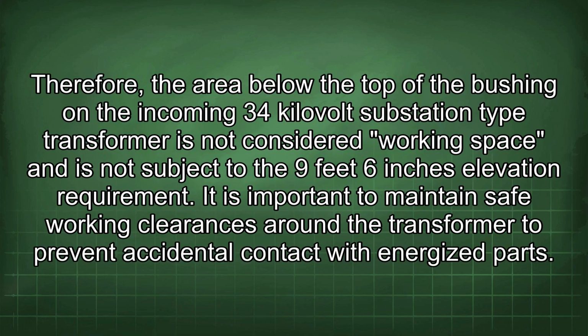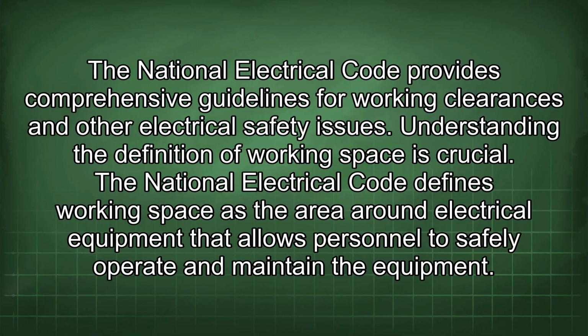Therefore, the area below the top of the bushing on the incoming 34 kV substation type transformer is not considered working space and is not subject to the 9 feet 6 inches elevation requirement. It is important to maintain safe working clearances around the transformer to prevent accidental contact with energized parts. The National Electrical Code provides comprehensive guidelines for working clearances and other electrical safety issues.